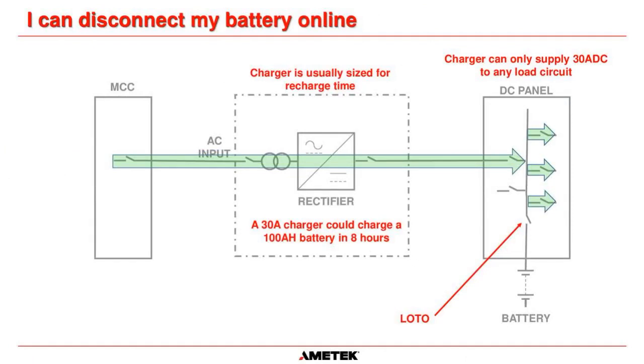A charger is usually sized for recharge time only. So let's say this battery here is a 100 ampere hour battery, okay? And the data sheet says that it needs 30 amps to charge that battery to get it back to 80% charge within 8 hours. That's the industry standard, okay? So therefore, most design engineers will say, okay, I'm going to make this charger, let's just say for ease, exactly 30 amps, okay?